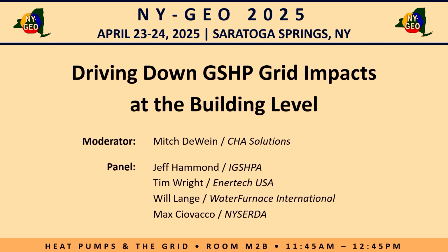Sure. Especially on commercial buildings, building automation systems really give us a lot of data, and it builds on what Will and Tim mentioned for their systems. That's really important, and it lets us measure how the systems are operating, but it also helps us with scheduling, if we're looking at peak demand or utility programs. The big advantage of ground source equipment, especially unitary equipment, multiple packaged units throughout the building, is you have that diversity of load, and also all that interconnecting piping. So if you have units heating and units cooling at the same time, you're just moving heat around.